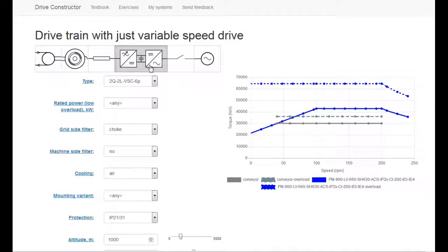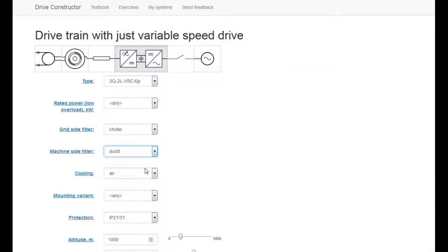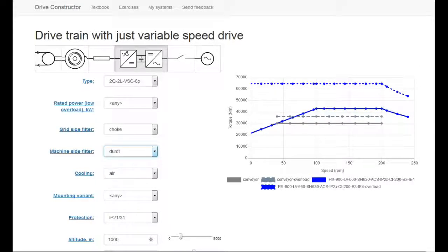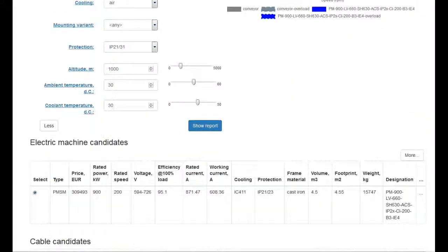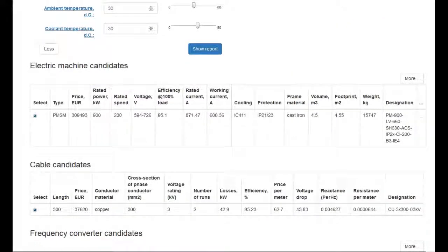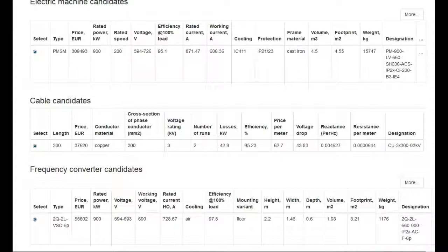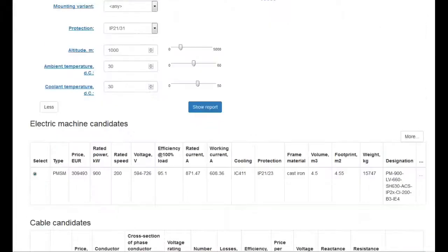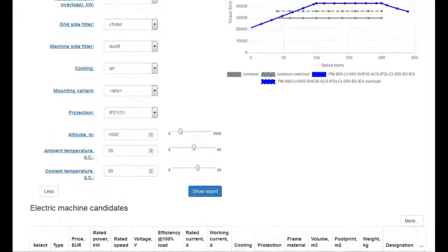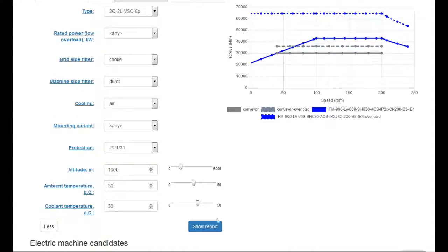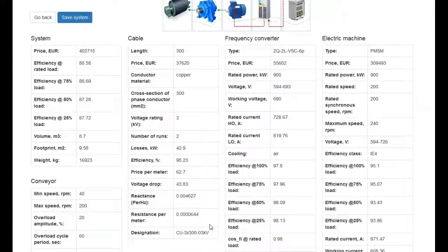Since we have the long cable, we most probably need an output filter for our frequency converter. So we choose a dU/dt filter, and now we see the frequency converter price went up because the filter is also expensive. So we see how the price is affected by the choice of the cable length, the cross section and the filters. Now we can go up and see what we get in the report.